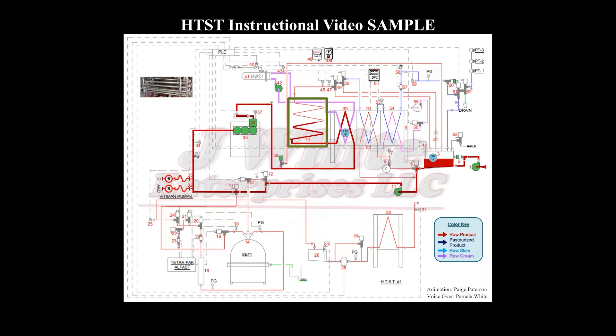Asset 44. The holding tube is where pasteurization actually occurs. The raw milk is held at or above the legal pasteurization cut-in temperature of 161 degrees for the legal minimum holding time of 15 seconds in the holding tube. Pasteurization temperature is set at 175 degrees on this HTST.